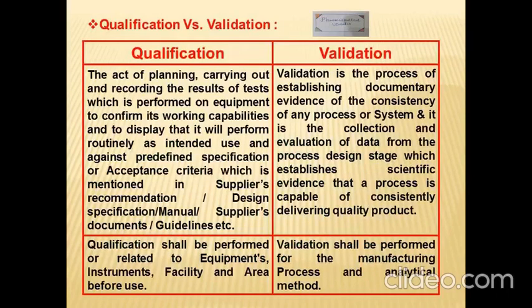Qualification is the act of planning, carrying out, and recording the results of tests which are performed on equipment to confirm its working capabilities and to display that it will perform routinely as intended use against predefined specifications or acceptance criteria.